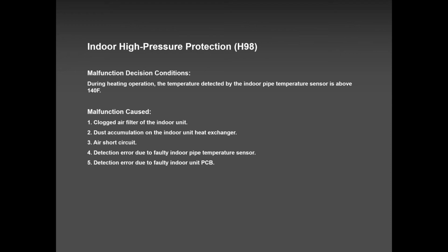It's the surface area that counts, as you know. The surface area of the outdoor unit is too large for just 1 indoor unit to operate. Hence, we get this H98. But again, H98 is just a protection. It's not going to lock out.